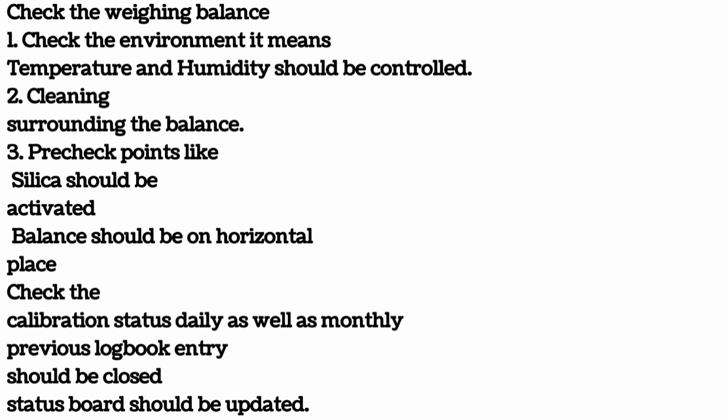Pre-checkpoints like silica should be activated. Balance should be on a horizontal place. Check the calibration status daily as well as monthly. Previous logbook entry should be closed and status board should be updated.